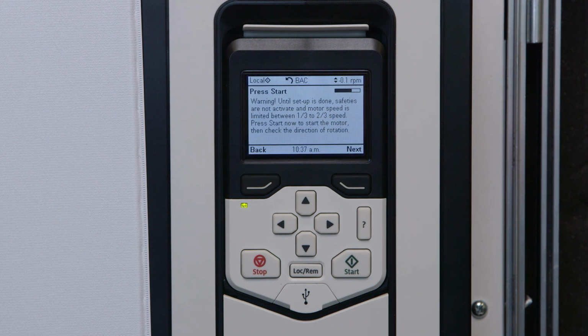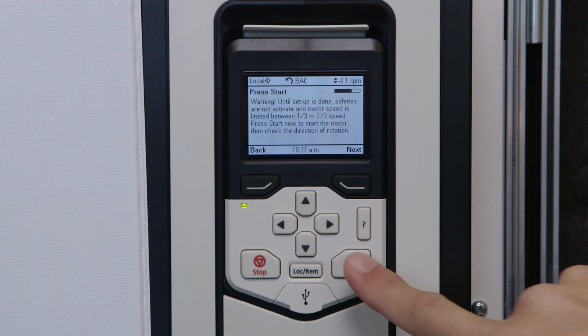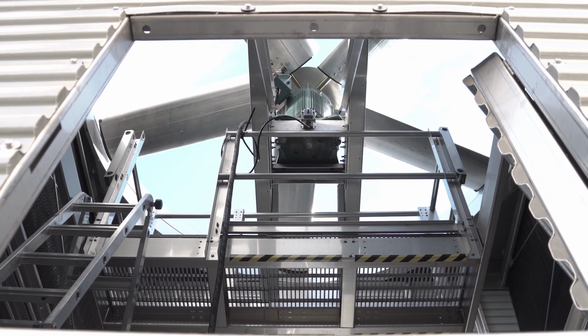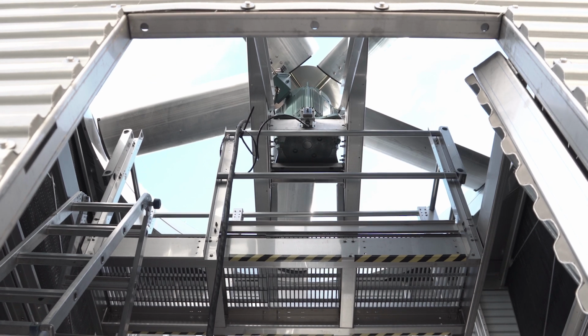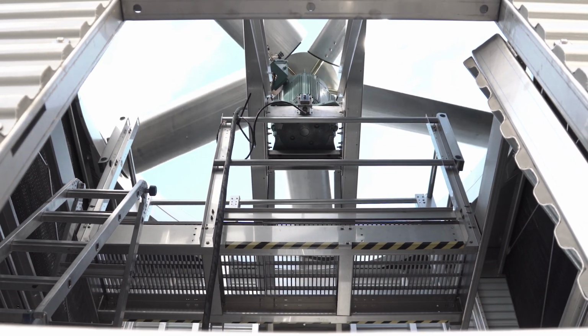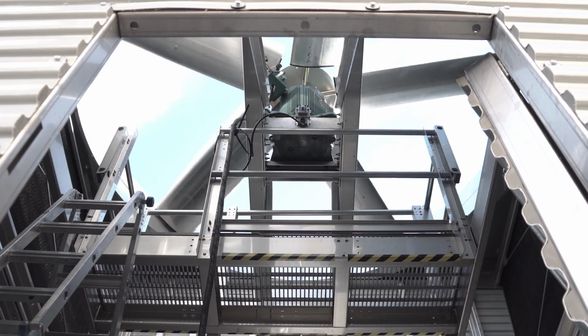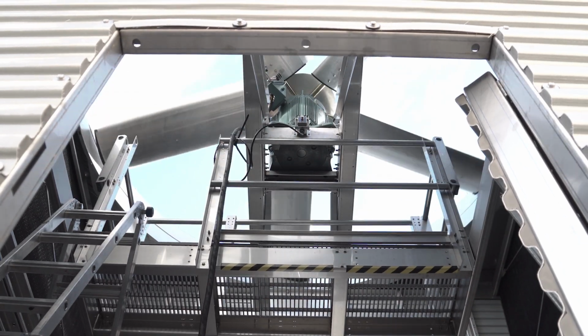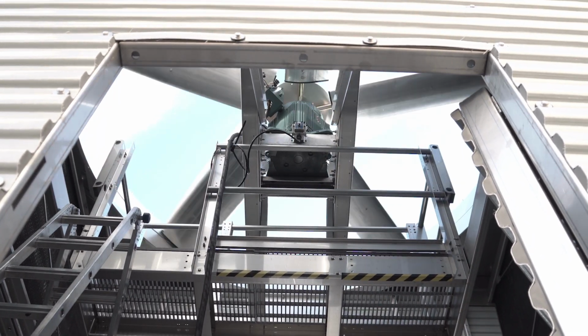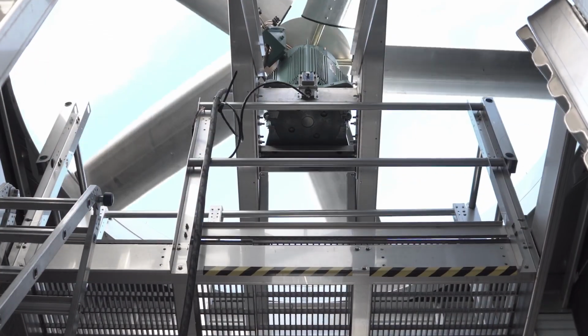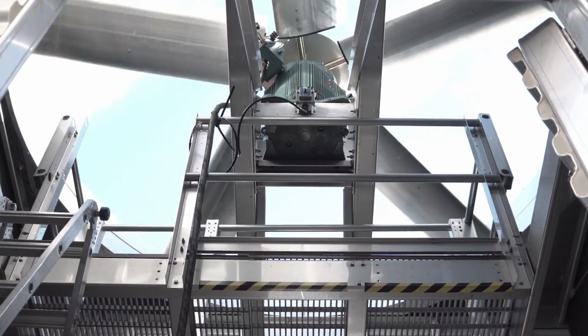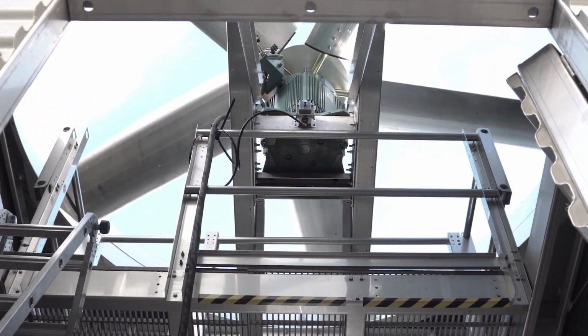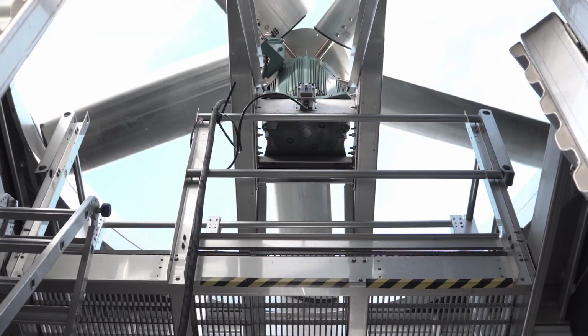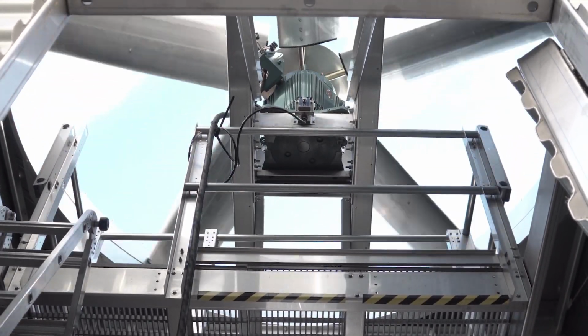Now, press the green Start button. On this command, the motor will begin a 15-second auto phase routine. This will be followed by the motor beginning to spin at 50 RPM. Have an assistant check the fan direction from outside the tower looking through the access door. He or she will need to look up and observe the direction of the fan rotation. The blade should be rotating in a counterclockwise direction and the air should be moving up.